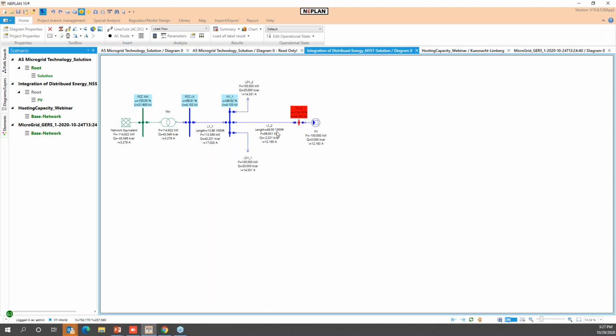That's a lot. So it is not as simple as just installing the PV facility or the wind facility and connecting it to the system. In this case, of course, we have the inverter set like a PQ, power and cos phi. So yes, we are fixing the generation here. If we run this PV facility as PV, we can support the voltage at 114, but we would require a lot of kilovar being injected from that source that we not necessarily could have.